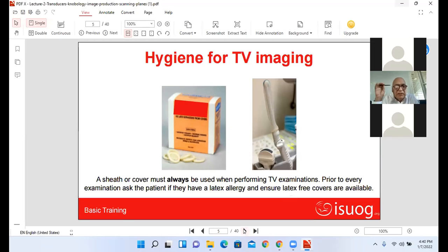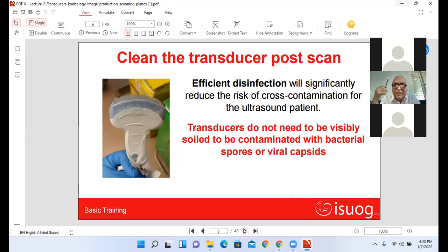Now, ultimately, the transducer is a valuable part, from where we send sound waves into the human body. So we have to be very careful and take utmost care. That is our golden tool, so we have to treat it as if it is our baby. Next slide, please. So we clean the transducer post scan again with the same wipe, and jelly should not be left like this. It is going to damage the footprint.